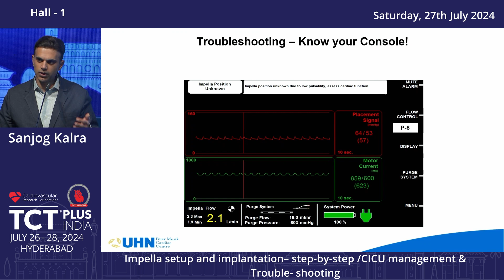So then the next thing you do is look at the echo, and you see that the device is in the aorta, which is why there's no differences between systole and diastole on your motor current. Okay? How about this case? Now you have a placement signal that looks aortic with good variability, but slow flows, right? Despite a high P level. So here you look at the placement signal, it looks appropriate. Is there variability in the motor current? Yes. Then step 3 is you always look at your hemodynamics.